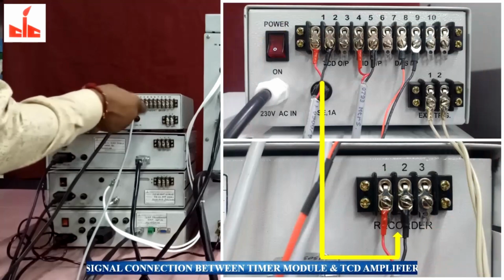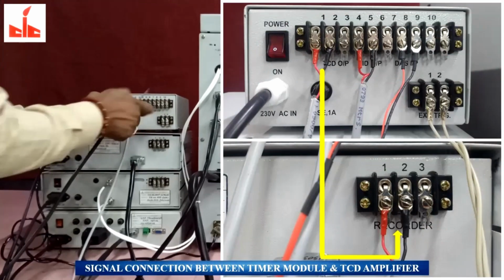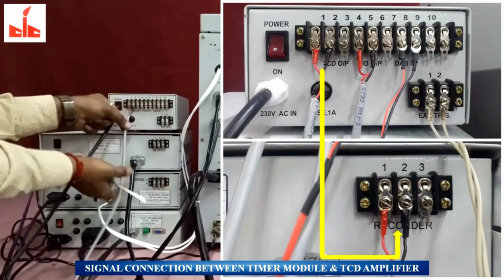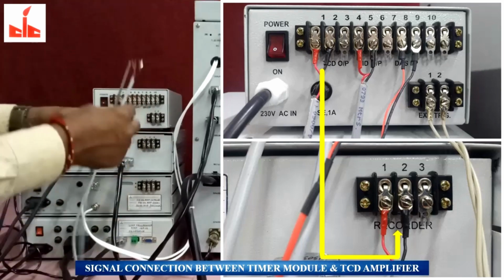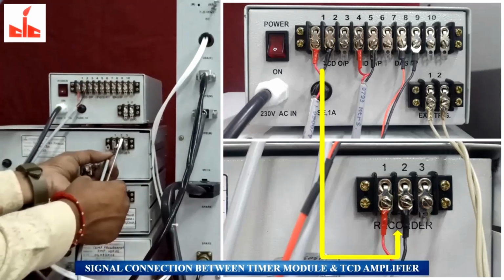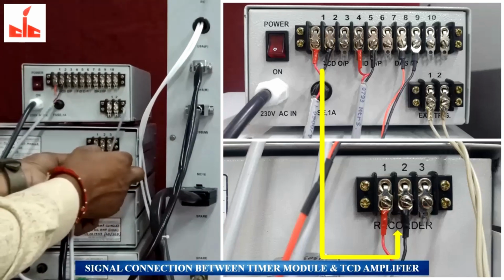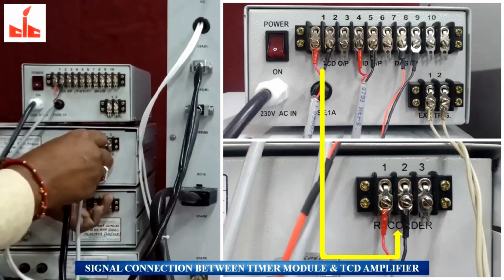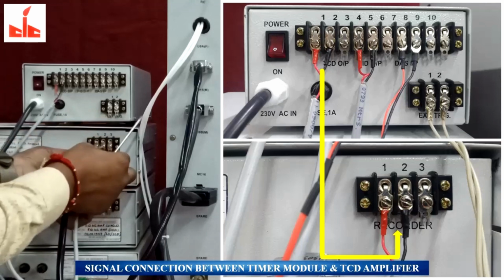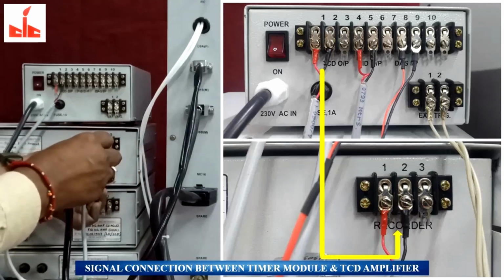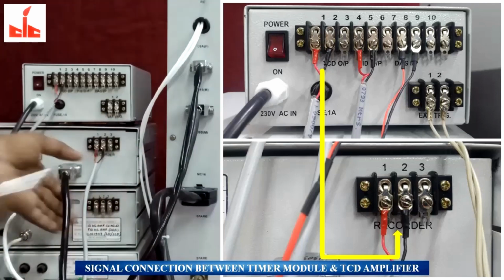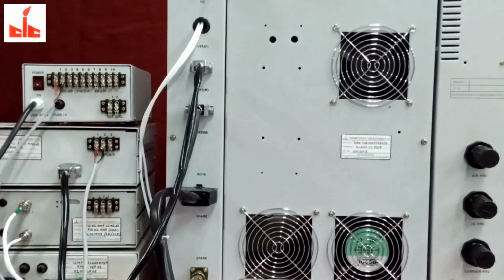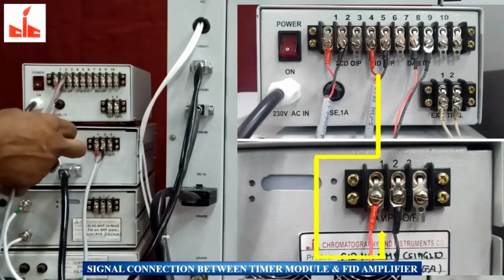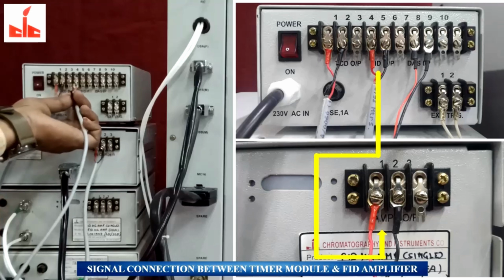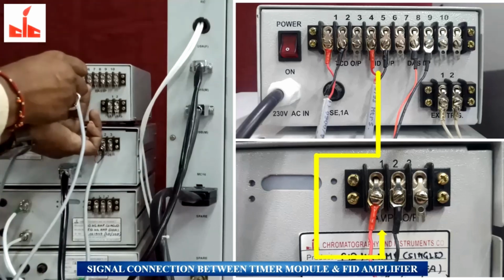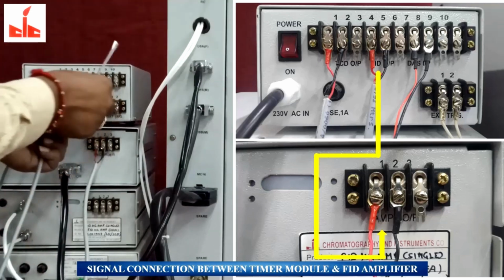Signal connection between timer module and TCD amplifier. Match the polarity as per picture. Use small screwdriver to open and close the screws of terminals. Signal connection between timer module and FID amplifier. Match the polarity as per picture.